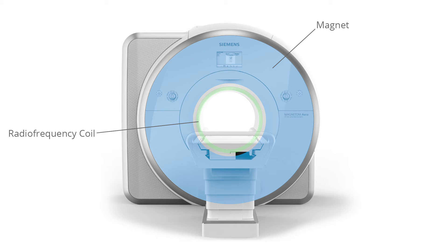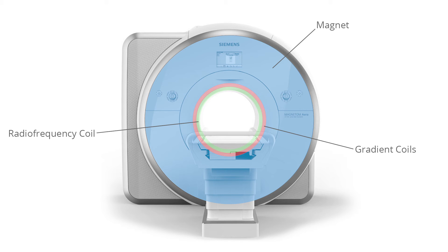As they do, the protons re-emit the energy that they absorbed from the pulse, and this signal is detected by the same radiofrequency coil. The gradient coils are switched on and off rapidly in a controlled sequence to locally perturb the main magnetic field, enabling spatial encoding of the signal such that thin slices can be imaged in any orientation and any location within the body.